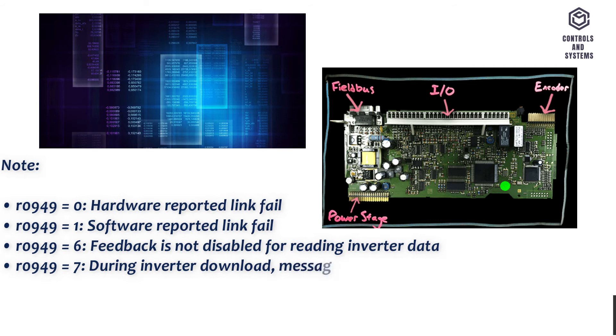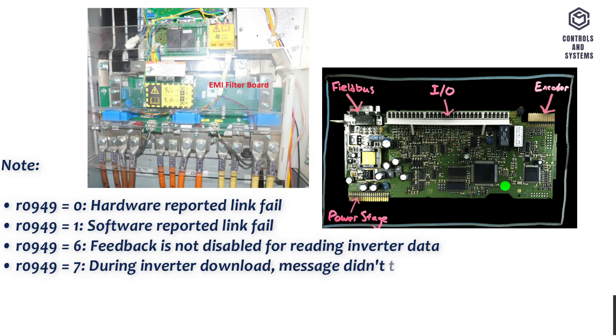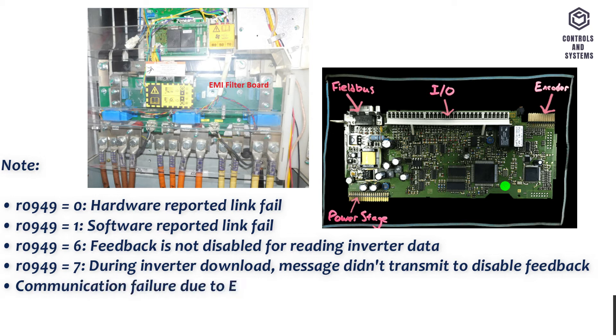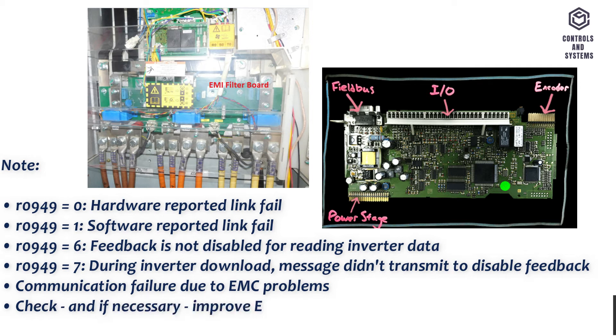R0949 equals 7: during inverter download, message didn't transmit to the data to disable feedback. Communication failure due to EMC problems. Check and, if necessary, improve EMC. Use EMC filter.